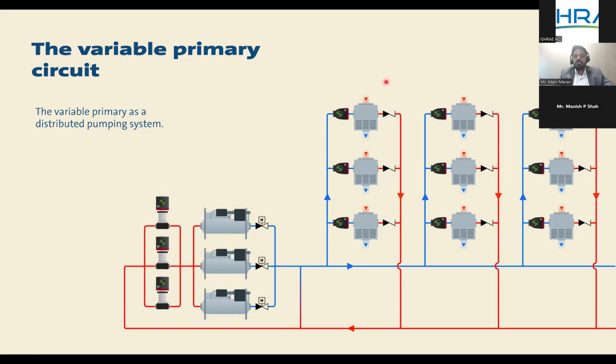Coming to the distribution side, which is the secondary side. Each unit, and when I say unit, it can be a fan wall unit or CRAH unit or CDU, will have its own dedicated coil pump connected to each unit. So the design of this pump is pretty simple. The flow of this pump is equated to the capacity of the unit, and the head of this pump is calculated to overcome the friction from the decoupler, which is basically from the start of the secondary loop. Let's say the head of this pump is calculated by taking the friction starting from this decoupler and the coil drop of this particular unit, any accessories, pipe frictions, and the return line back to the decoupler. That's the head of this pump.